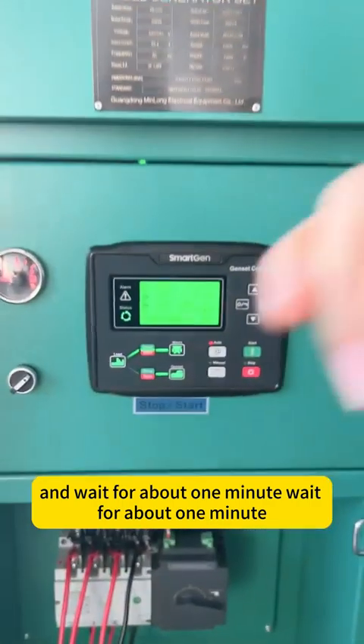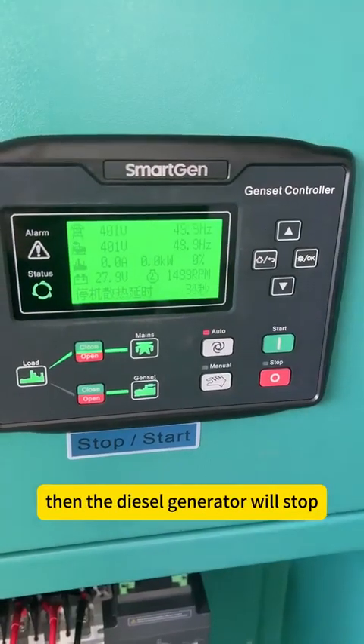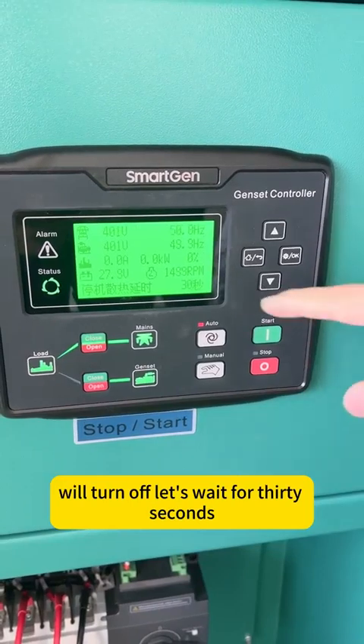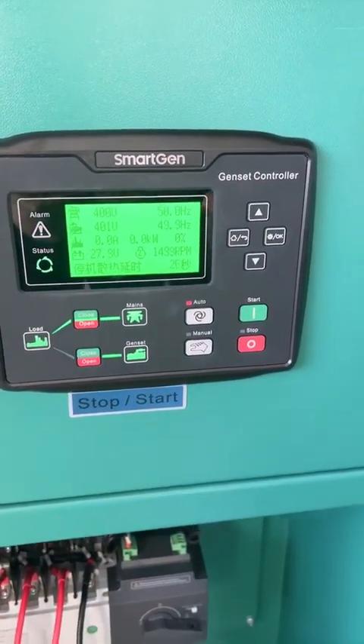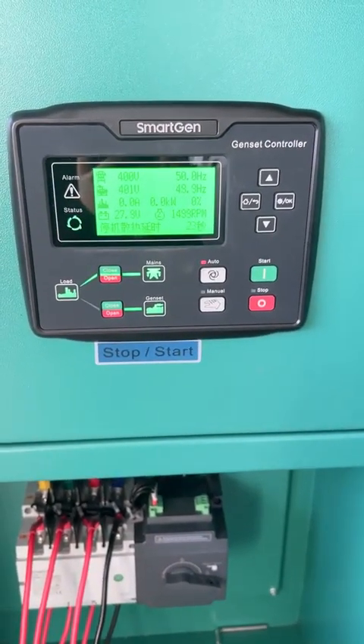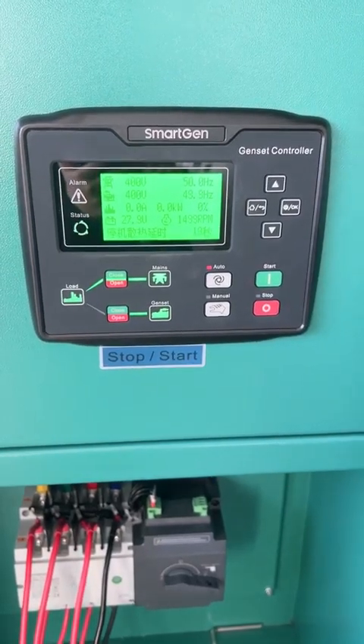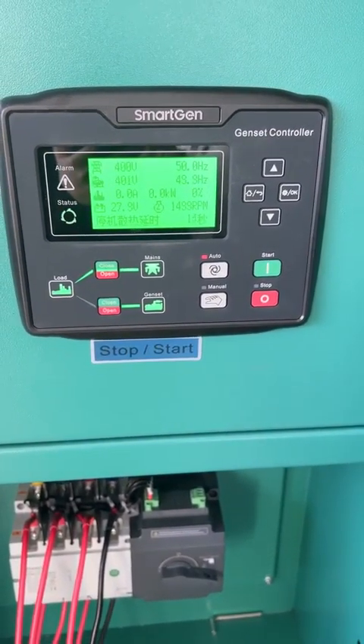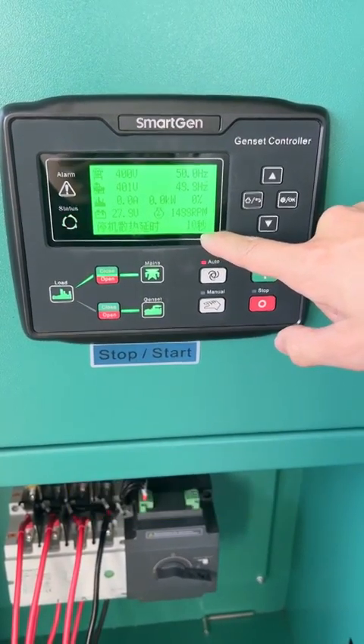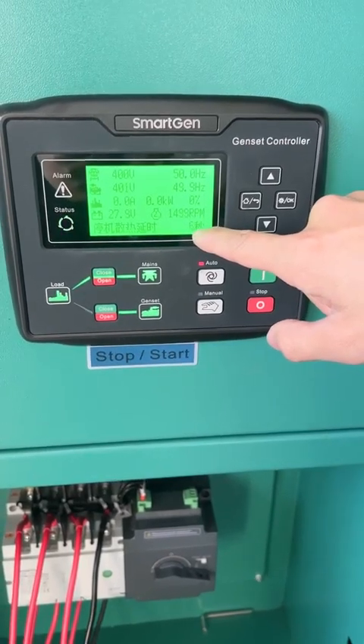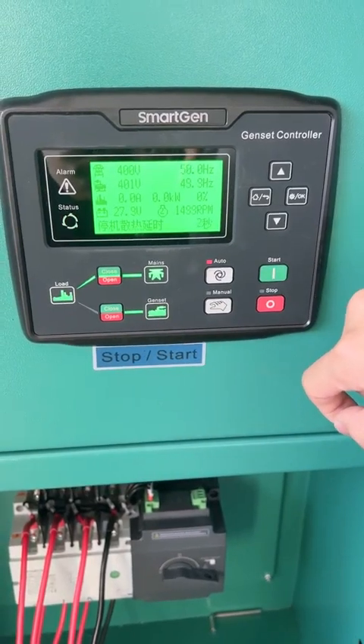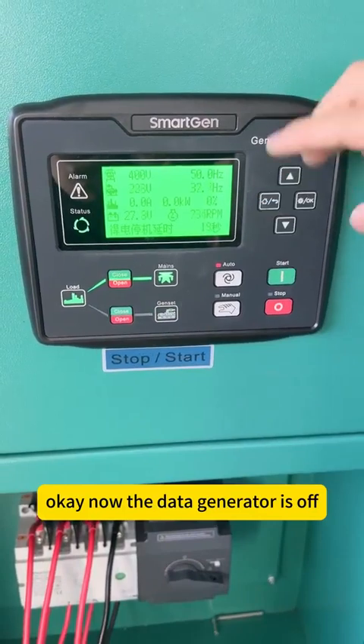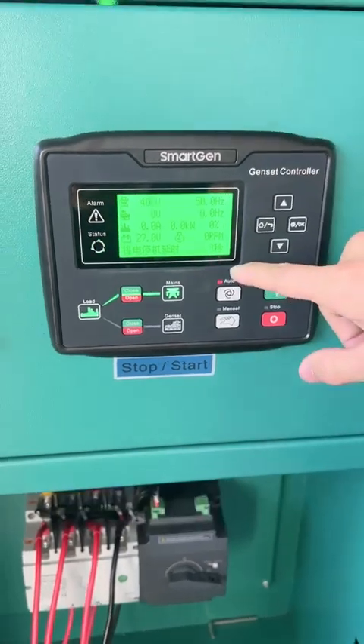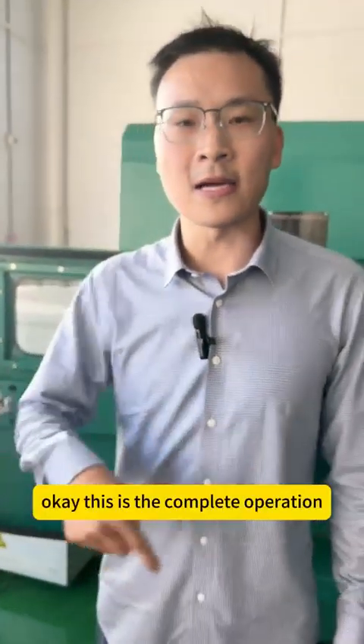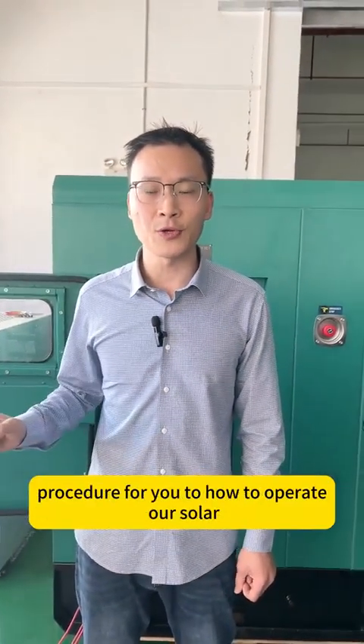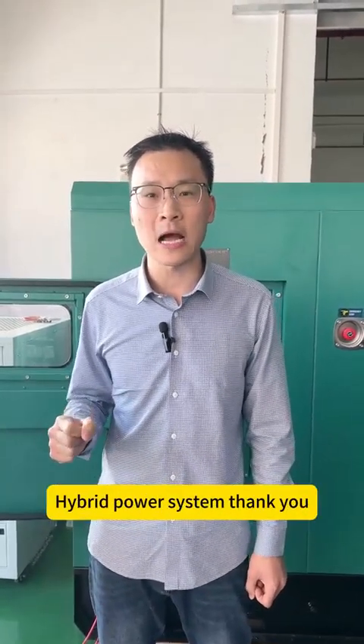Now the inverter is using grid power to take the loads. And wait for about 1 minute. Now still 36 seconds. Then the diesel generator will turn off. Let's wait for 30 seconds. Now still 10 seconds. Okay, now the diesel generator is off. This is the complete operation procedure for how to operate our solar and diesel generator hybrid power system. Thank you.